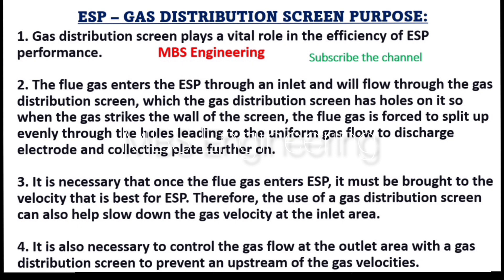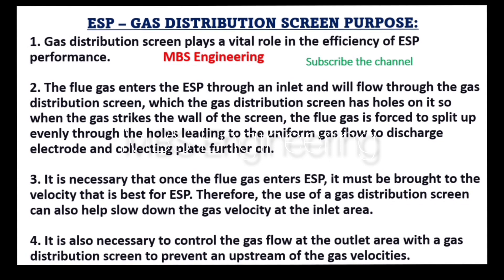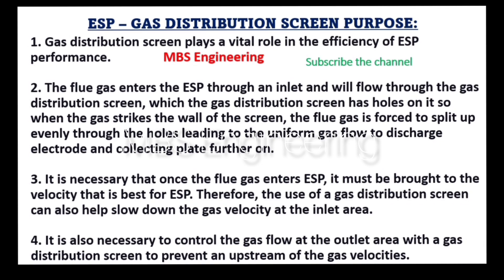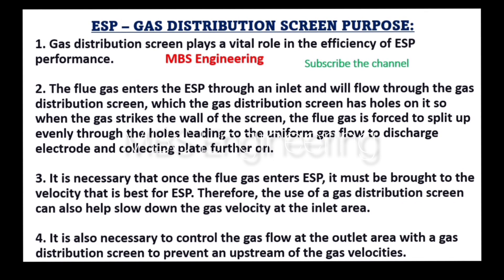Now we understand the purpose of the gas distribution screen in the electrostatic precipitator. Point 1: The gas distribution screen plays a vital role in the efficiency of ESP performance. Point 2: The flue gas enters the ESP through an inlet and will flow through the gas distribution screen, which has holes on it. When the gas strikes the wall of the screen, the flue gas is forced to split up evenly through the holes, leading to uniform gas flow to the discharge electrode and collecting plate further on.